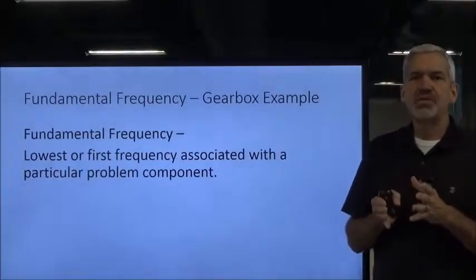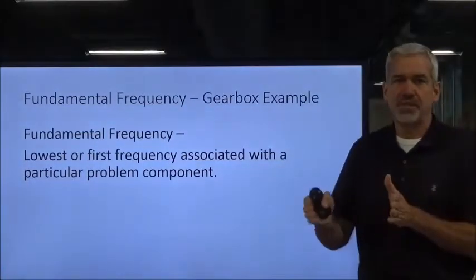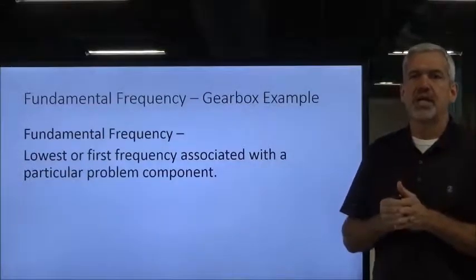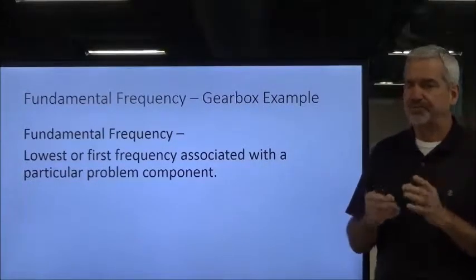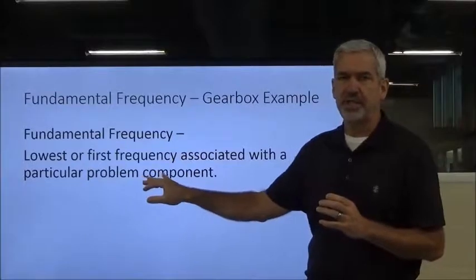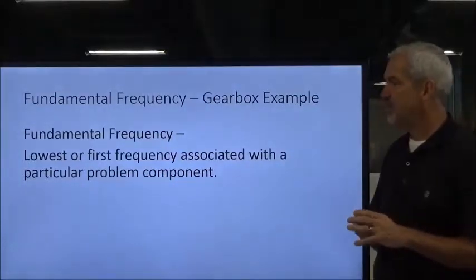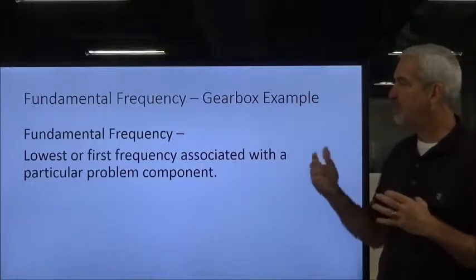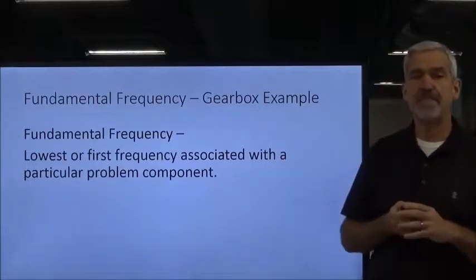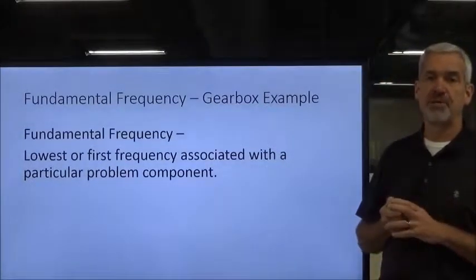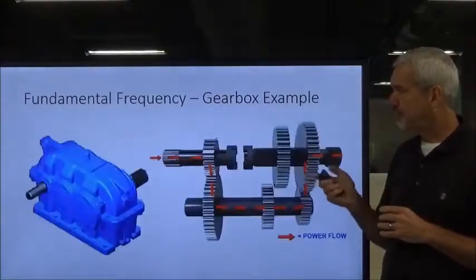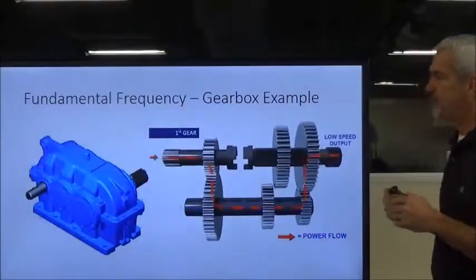That is the lowest or first order of frequencies in a particular component. You use these a lot in bearings and gears. Again, the definition is the lowest or first frequency associated with a particular problem component. Let's use the graphics here for just a minute.